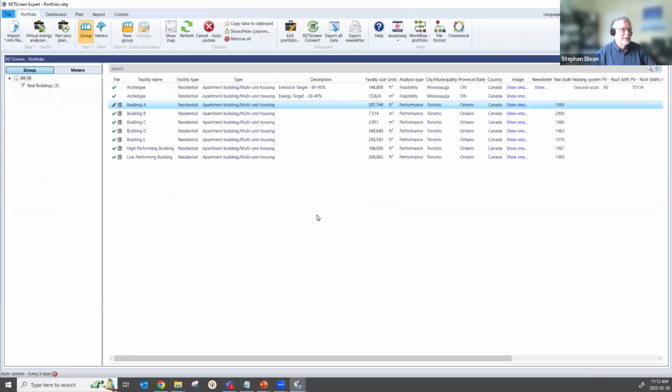All right. There's a couple of questions there in the question and answer. Can a CUSUM be done on hourly data, or does it make sense only for monthly or yearly data? Yeah, so the CUSUM requires a regression to begin with. Now, in RETScreen, that's the way you traditionally would do a CUSUM, is you would have a regression behind it. But having said that, that would limit it to daily, weekly, monthly data, okay? Because on regressions the minimum resolution is a day.